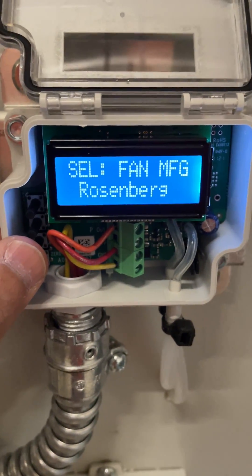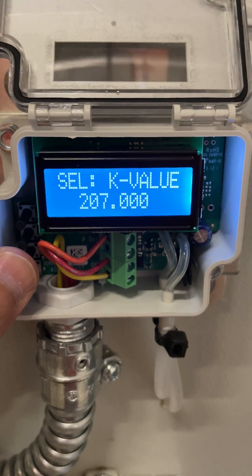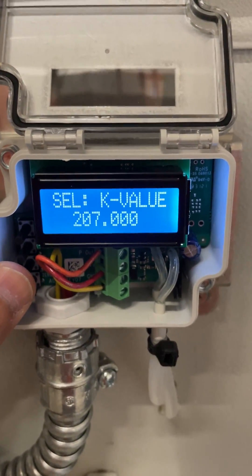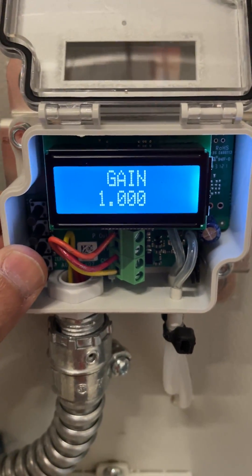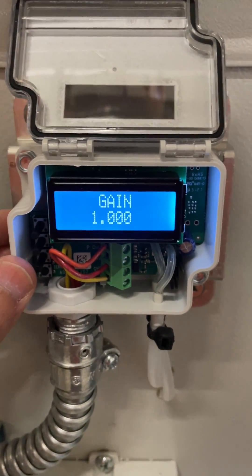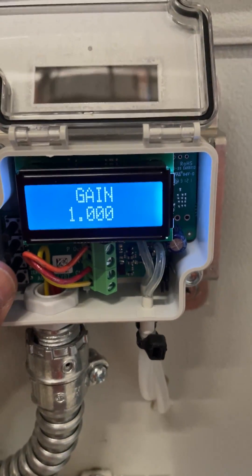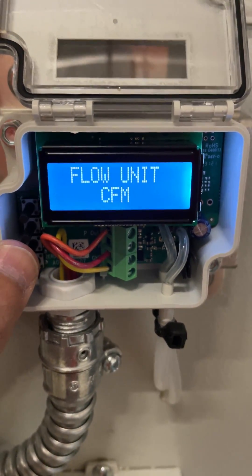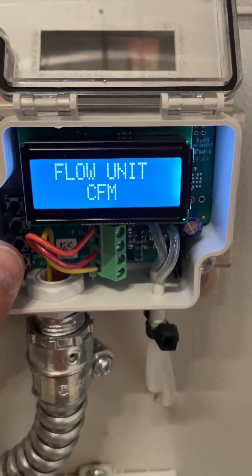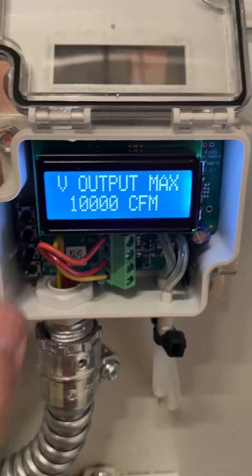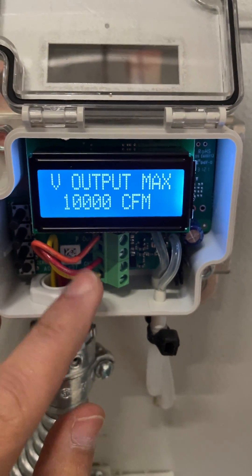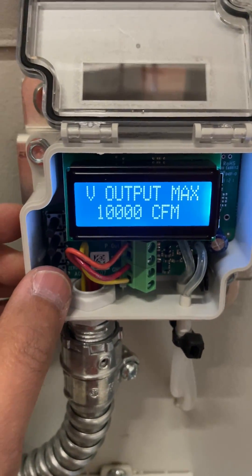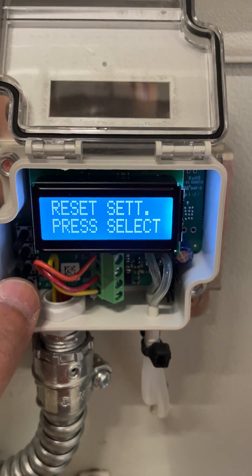In my project I'm using Rosenberg. The K value you have set up — you will get that from your engineering data. The gain will be provided once your balancer comes in and measures it so that it matches the actual flow. You can also set up the pressure unit, the max output, the flow unit, and the V output max is what you'll be getting as an output. You can set it up according to your characteristics in your software.